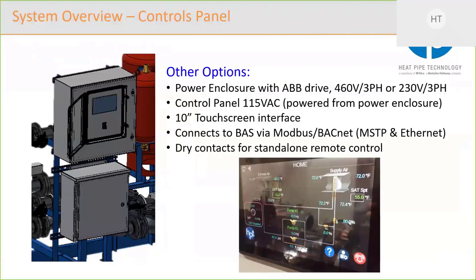And it also runs alone. So if you're a customer who is very keen on making sure that the system is hooked up to your building automation system and communicating both ways, we can do that. If you're a customer who is maybe limited on your controls budget, we can give you exactly the same system and it'll operate perfectly as a standalone system. We also offer some dry contacts. So if you don't have a BMS and you need to have some alarms or activate other things, we do have some dry contact outputs, and I'll touch on those in a slide or two.